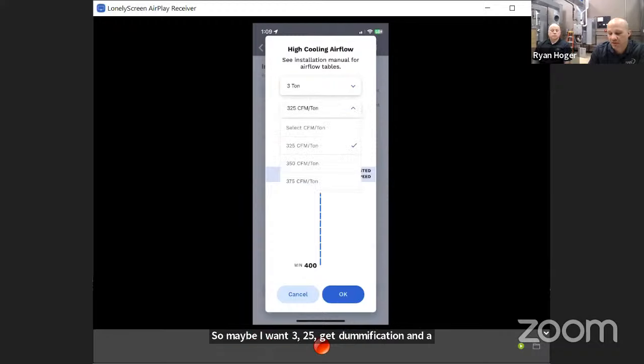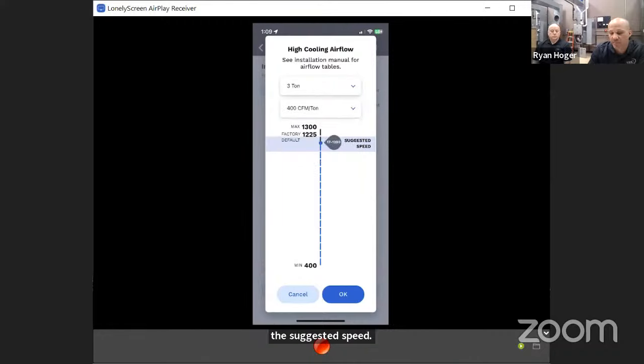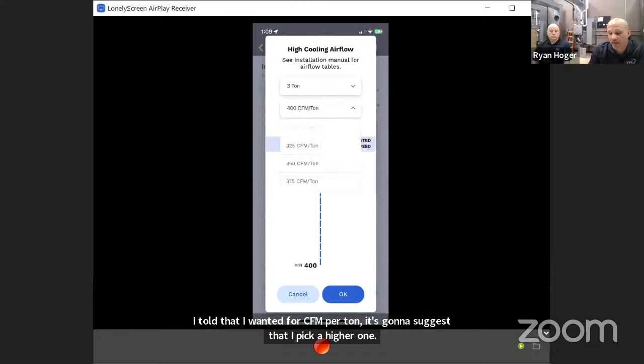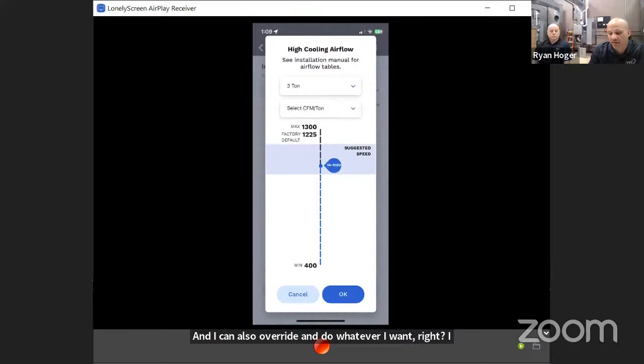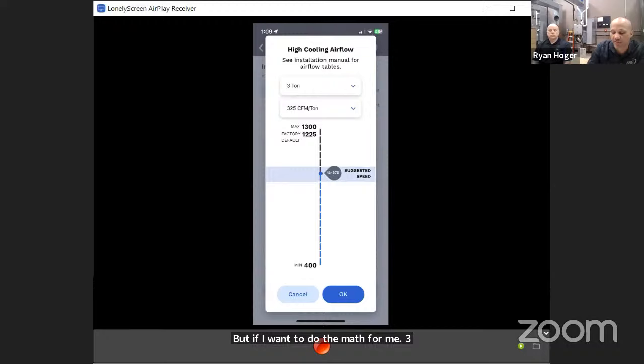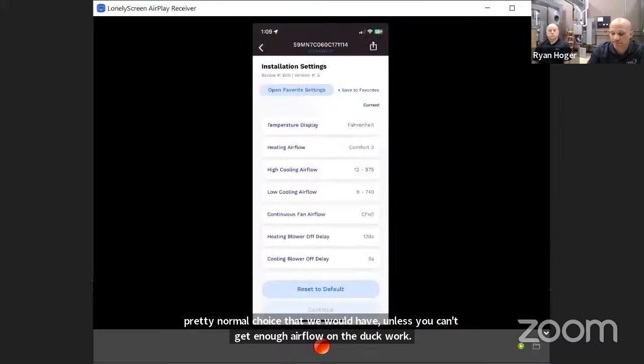the suggested speed. If I told it I wanted 400 CFM per ton, it's going to suggest that I pick a higher one. And I can also override it and do whatever I want, right? I can make my own choice and slide it up and down. But if I want to do the math for me, 325 per ton is a pretty normal choice that we would have, unless you can't get enough airflow on the ductwork. Once you get it the way you want, you say, okay, right?